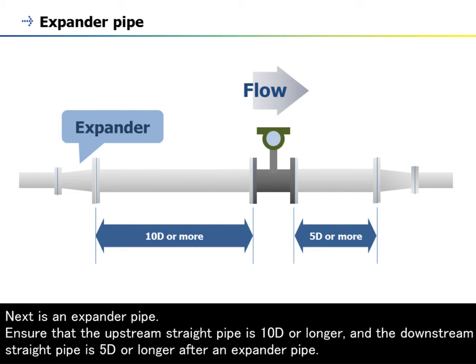Next is an expander pipe. Ensure that the upstream straight pipe is 10D or longer, and the downstream straight pipe is 5D or longer after an expander pipe.